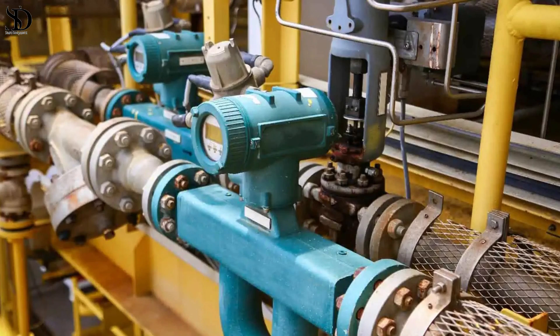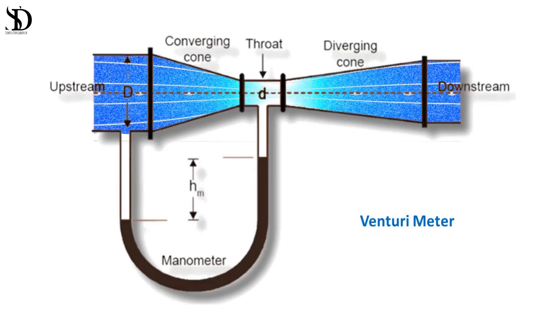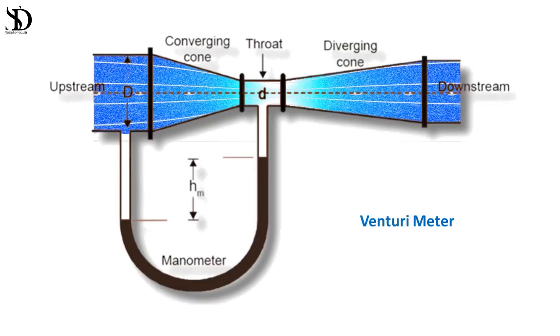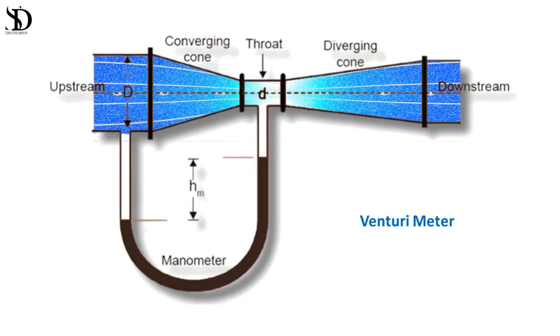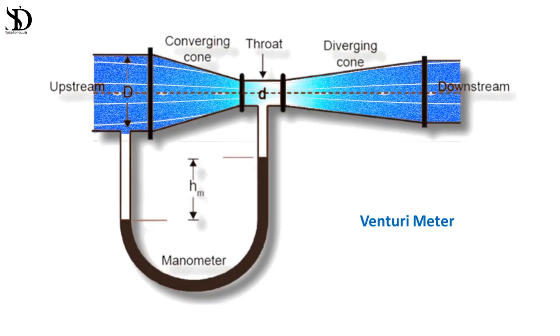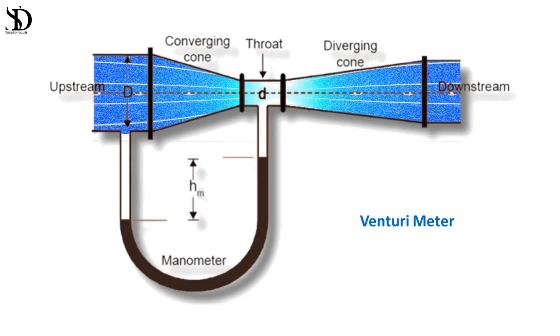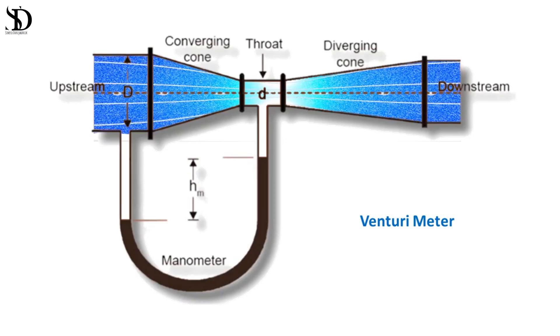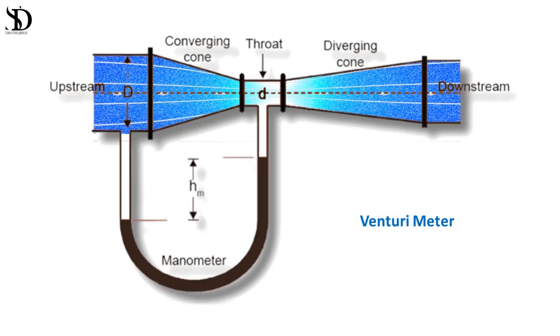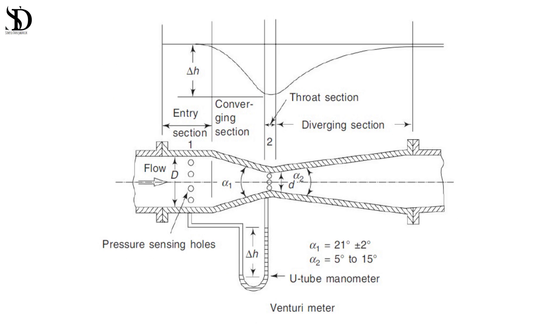Venturi tubes principle: venturi tubes are more complex than orifice plates, featuring a converging and diverging section in the pipeline. The constriction causes an increase in flow velocity leading to a decrease in pressure that can be measured to calculate the flow rate accurately.